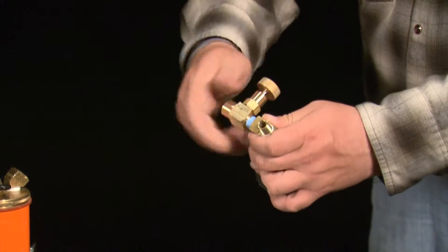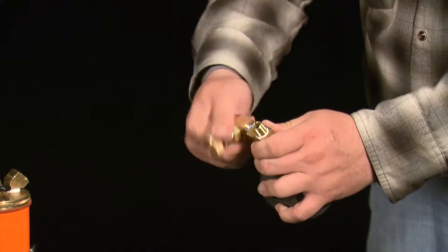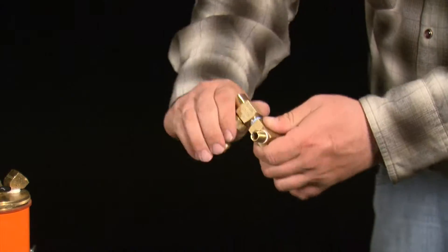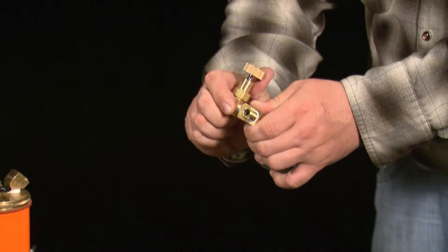Screw the new needle valve onto the brass elbow where the pop valve used to be. Make it sit at a 90 degree angle to the elbow and gauge and fit snugly.